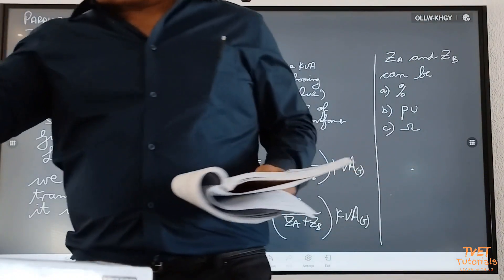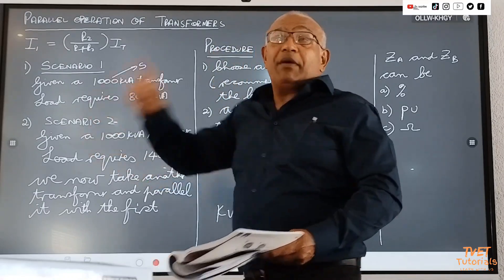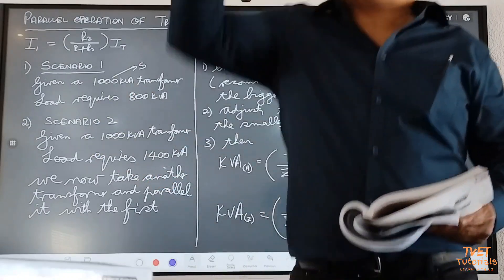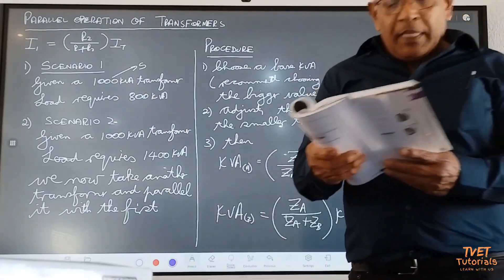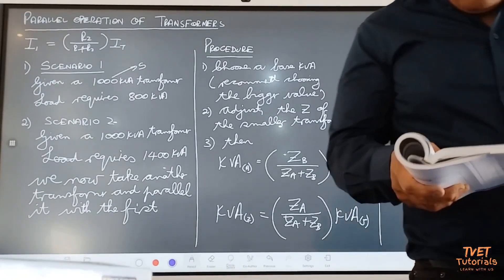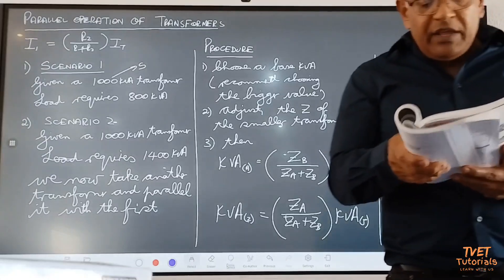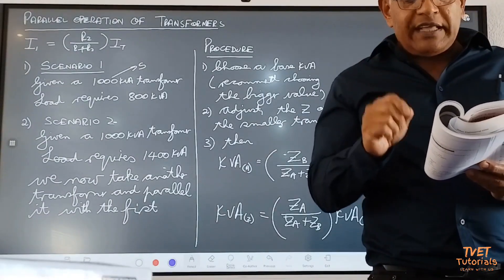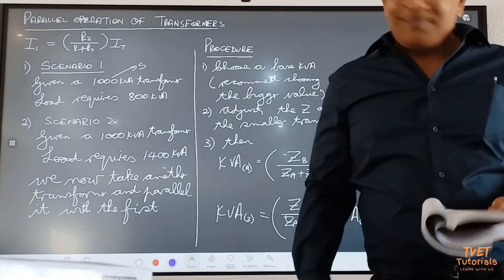Because transformers are rated in kVA, we work only with kVA. Therefore, if the load that needs to be supplied is given in kilowatts, you must convert to kVA — you divide by the power factor. Convert the load to kVA by dividing the power by the power factor.